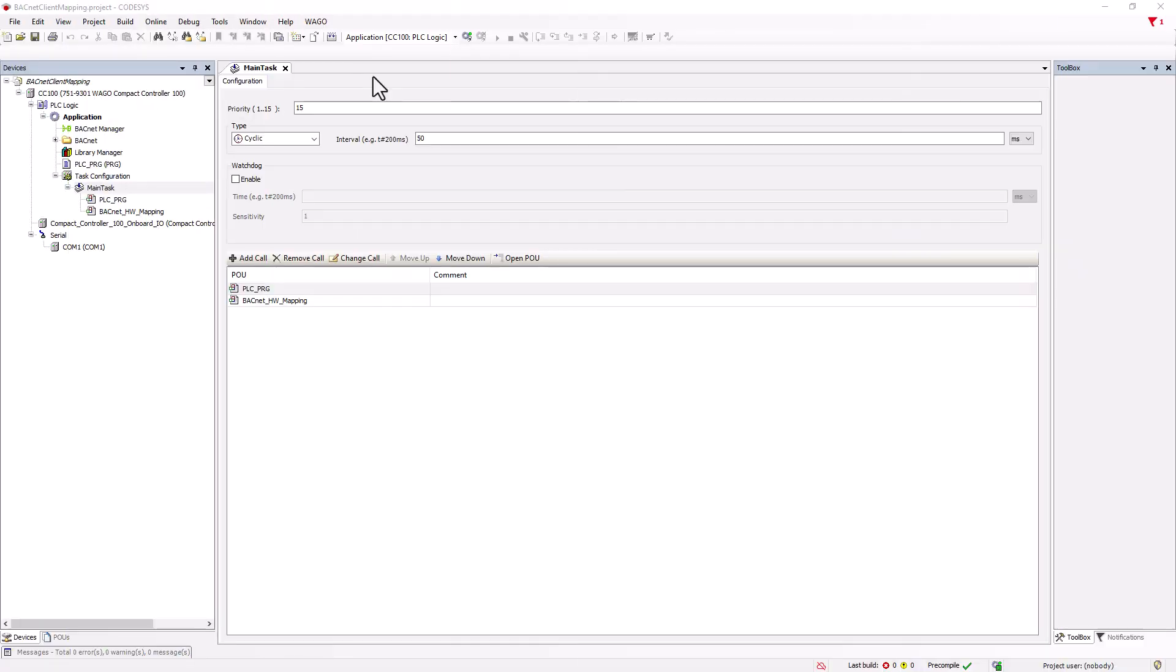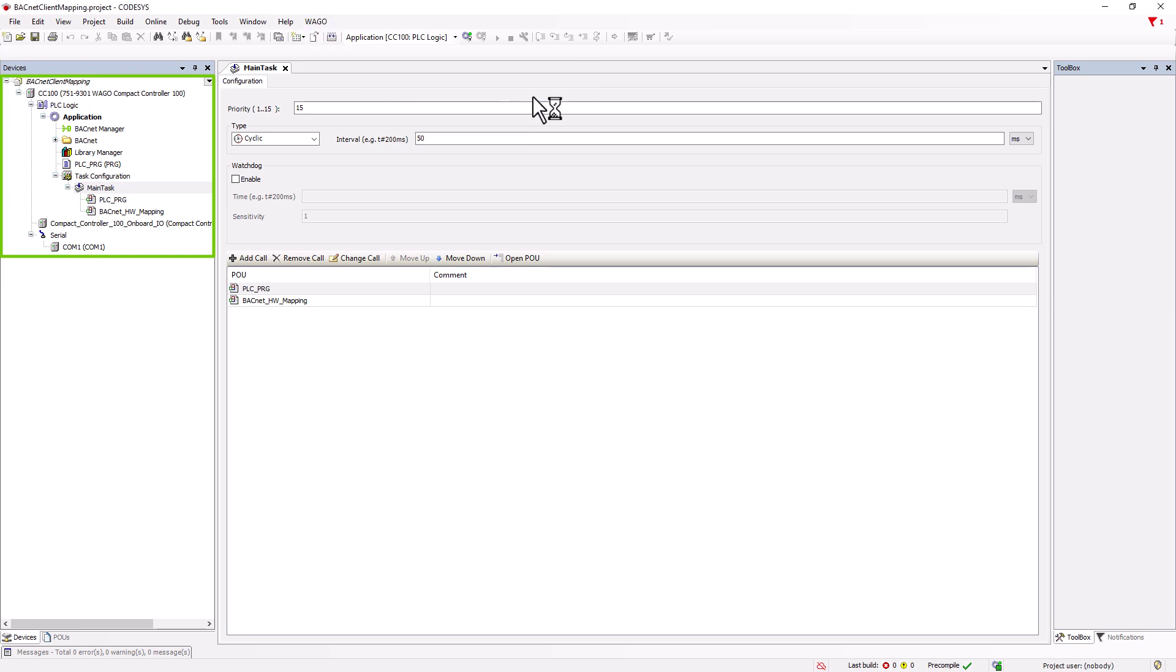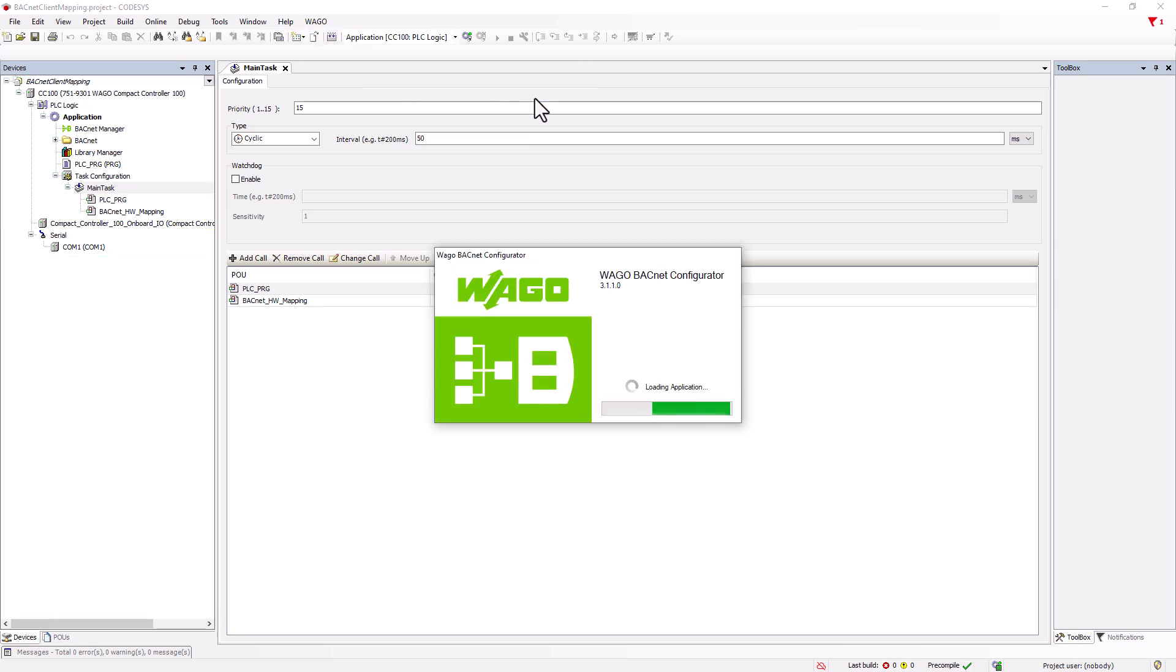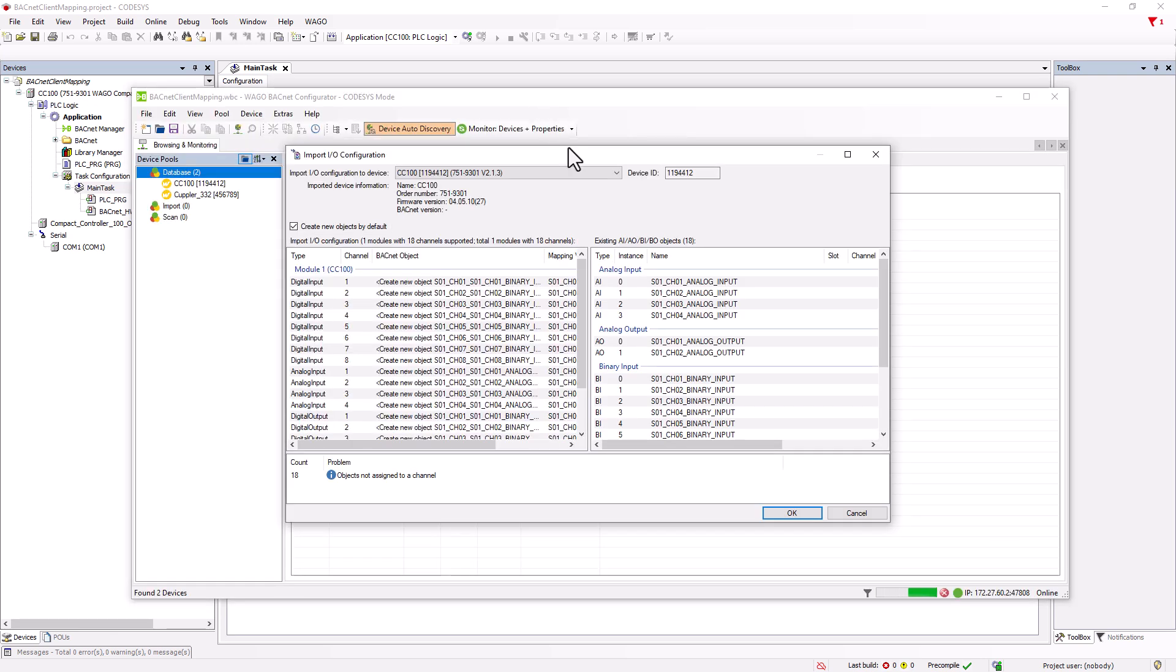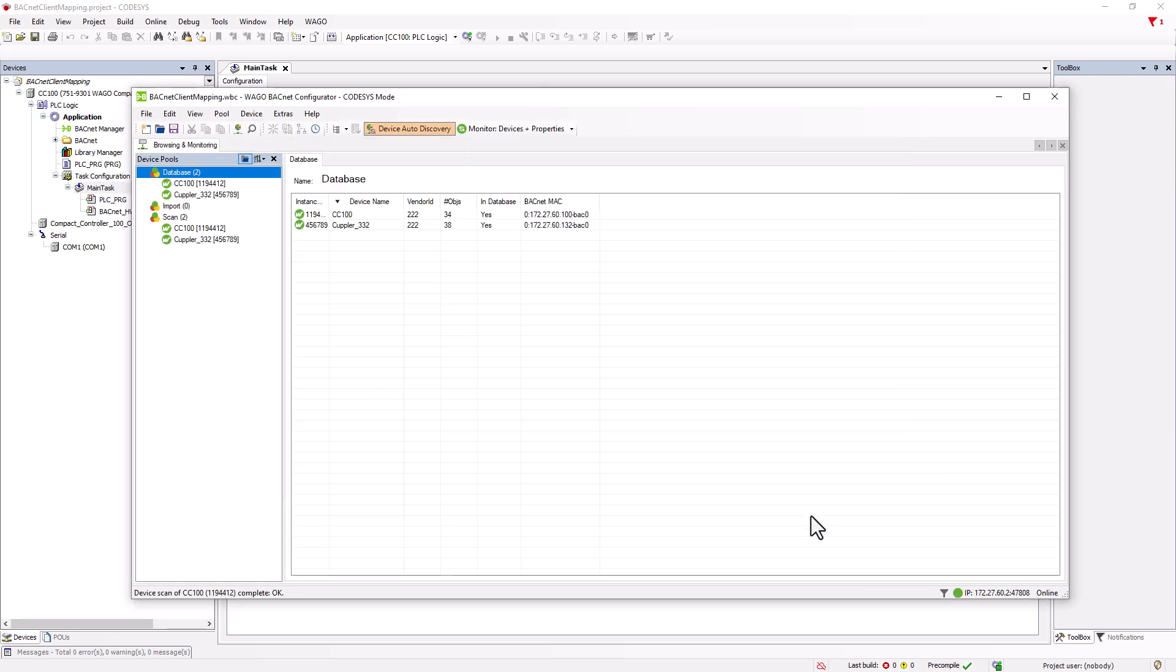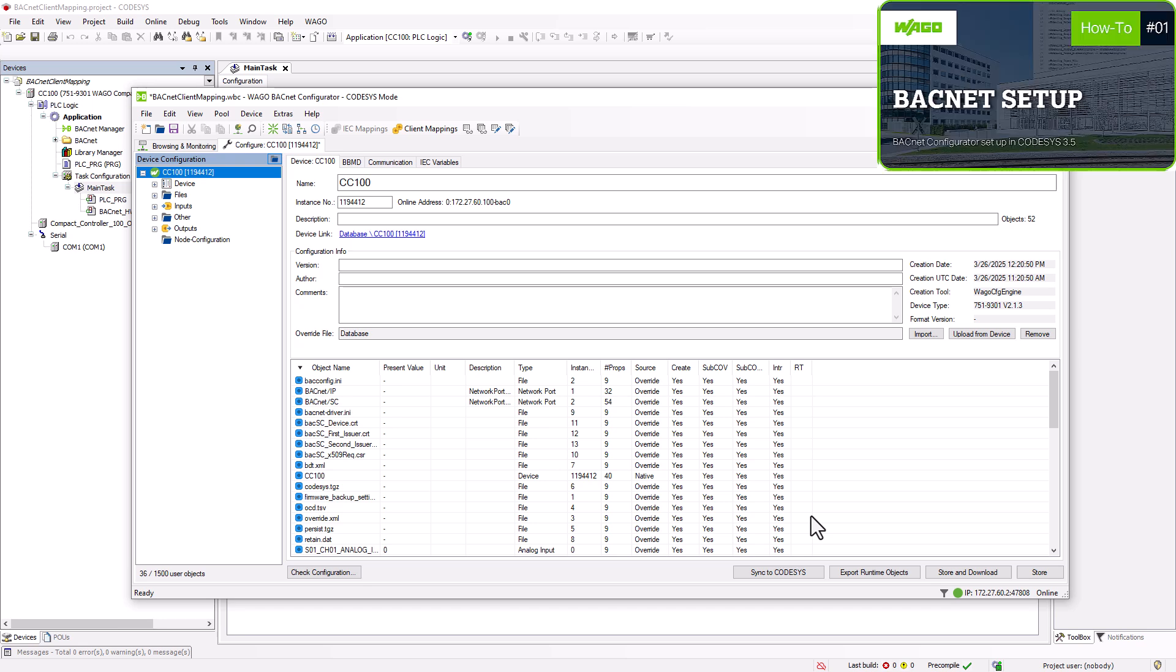The WAGO BACnet configurator can recognize the coupler with all connected modules and consequently the corresponding BACnet objects. This is not the case with the CC100, so it is advised to first create a CODESYS 3.5 project and start the WAGO BACnet configurator from there. This allows the appropriate BACnet objects for the hardware inputs and outputs to be created, linked and transferred to the WAGO BACnet configurator. A detailed tutorial on this process is part of the tutorial BACnet configurator setup in CODESYS 3.5. A link is provided in the video description.